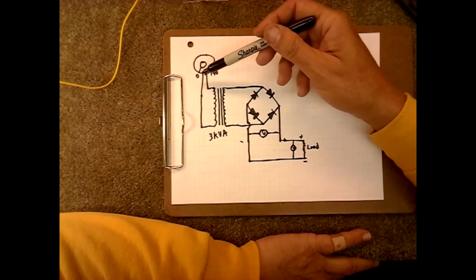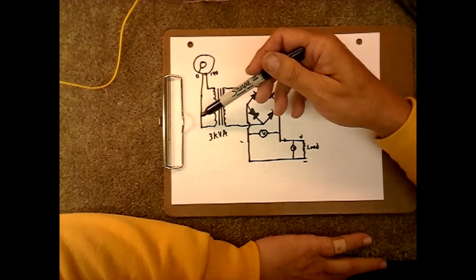That stray voltage goes away if you tie a load in here. Then if you measure the voltage across here, you have no AC—just pure DC, and it's no longer ridiculously high. I was getting high DC voltage readings with my Variac at 0 and the switch on; there's a current limiting bulb here, which is switched out for this particular circuit.